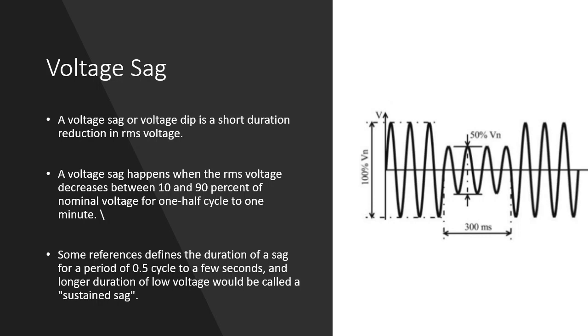So when my voltage value decreases, that's a voltage sag. This occurs for at least half a cycle up to one minute — or in some cases from 0.5 cycles to a few seconds. If it exceeds a few seconds, we call it a sustained sag. Voltage sag is also known as voltage dip or voltage drop, and it is the most common issue in voltage problems.